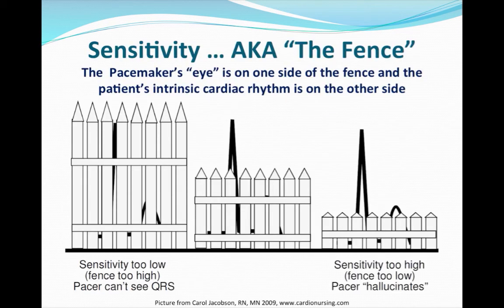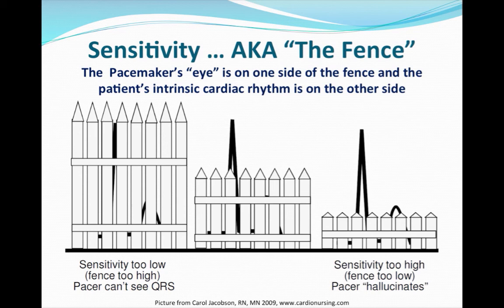The sensitivity allows the pacemaker to see what's going on inside the heart. Think of it as a fence — the pacemaker eyeball is on one side and the cardiac rhythm is on the other. We want the fence low enough so the pacemaker can see the QRS. If the fence is too high, the pacemaker can't see the rhythm and will send impulses when the patient doesn't need it. If the fence is too low, the pacemaker may see P waves, QRS's, T waves, or artifact and think it doesn't need to pace when it actually does.